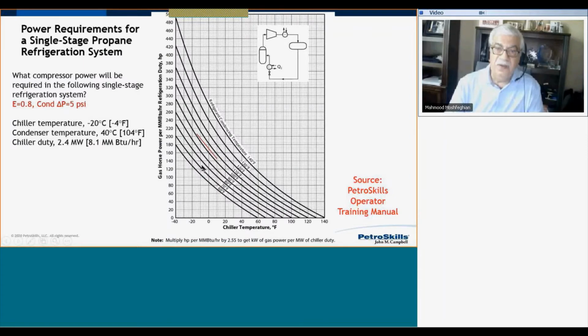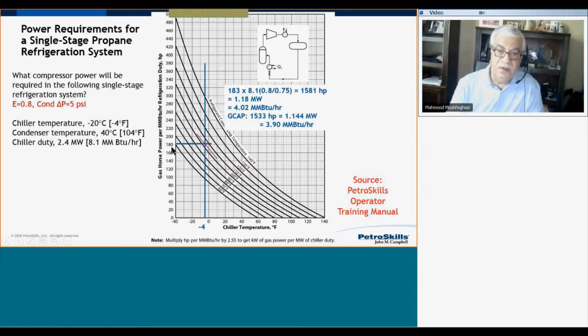We can determine the power requirement for this compressor using this chart, which is from our operator training manual. This is for simple refrigeration system with single stage of compression. All I have to know is the condensing temperature, so 104 degrees Fahrenheit, and the chiller temperature, which I already know. My chiller temperature is -4 degrees Fahrenheit.